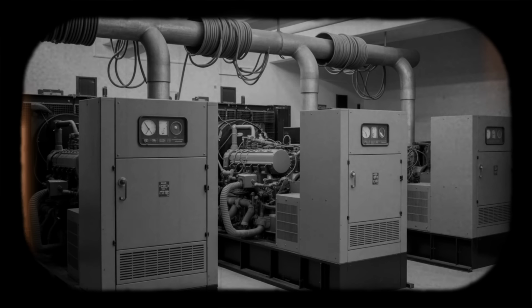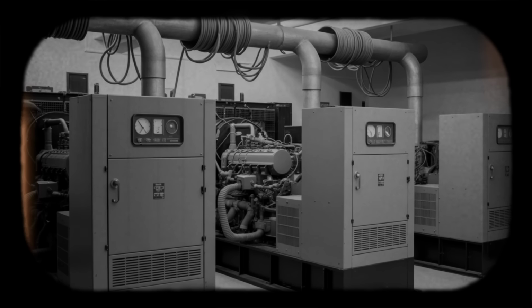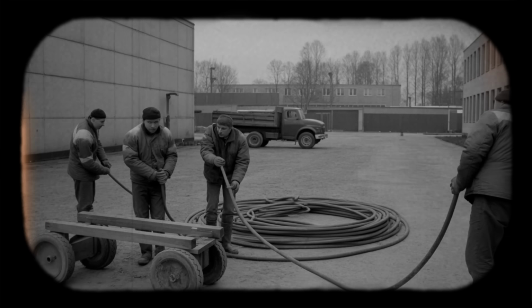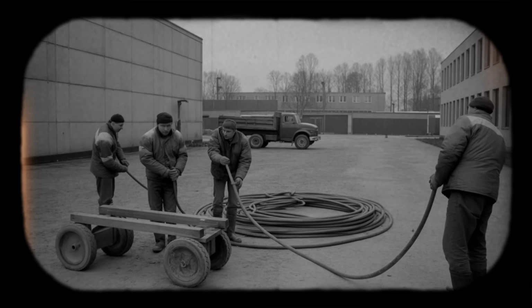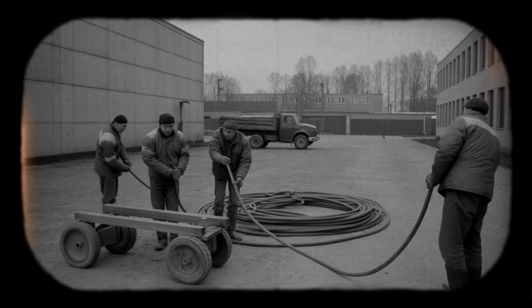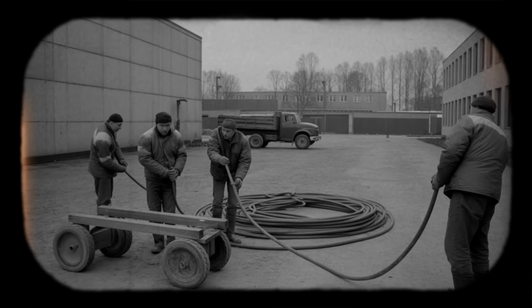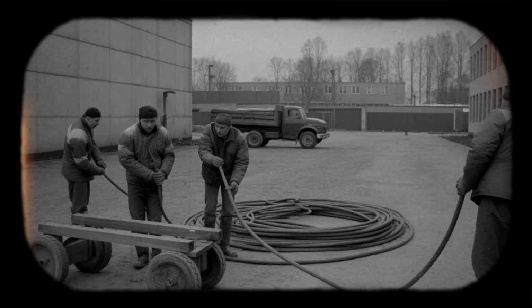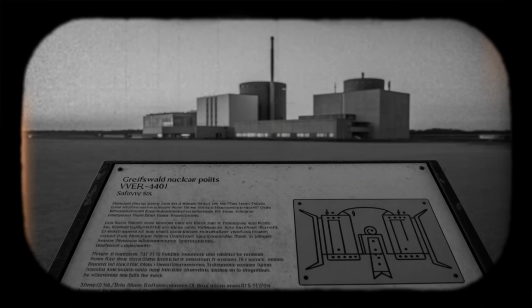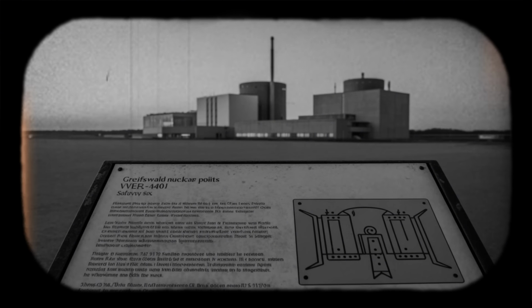Human factors became central. With limited data, operators accepted non-standard measures, using boron pumps for cooling, accepting a cross-connection from another unit, operating for hours without full indication of primary system conditions. These decisions required confidence, engineering judgment, and a willingness to step outside procedural boundaries when procedures no longer matched reality. Later fire probabilistic safety assessments would explicitly model loss of indication as a separate contributor to core damage probability, in part because of lessons from Greifswald. The event showed that instrumentation vulnerability deserves the same analytical rigor as equipment vulnerability.